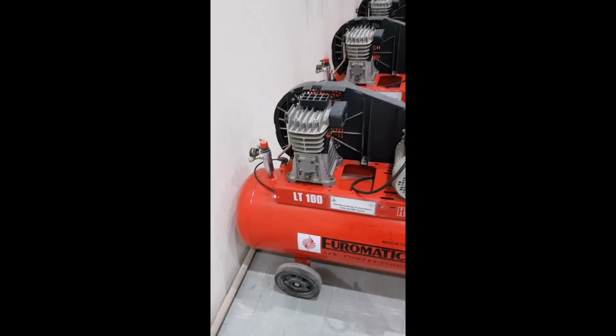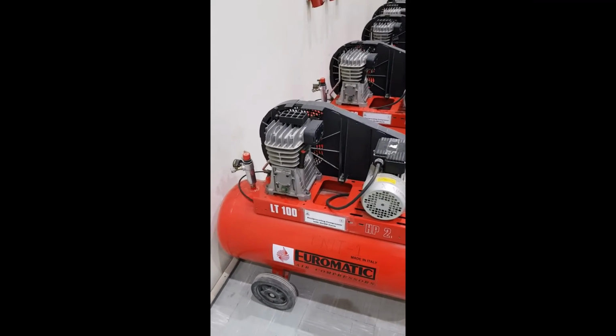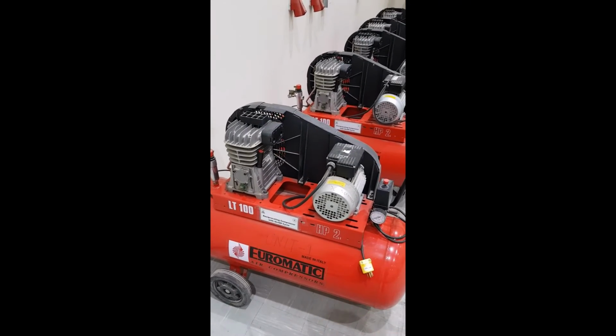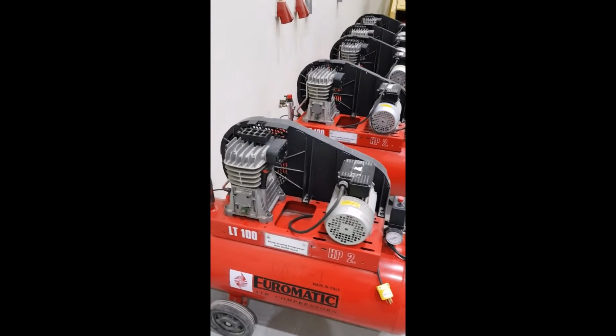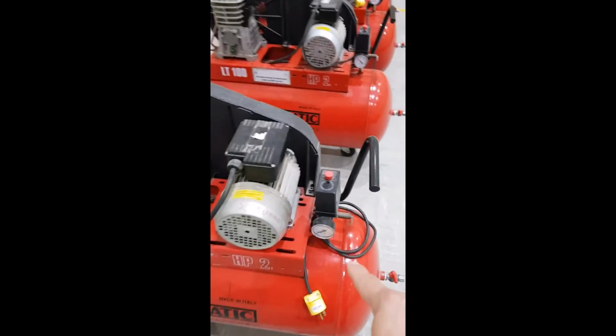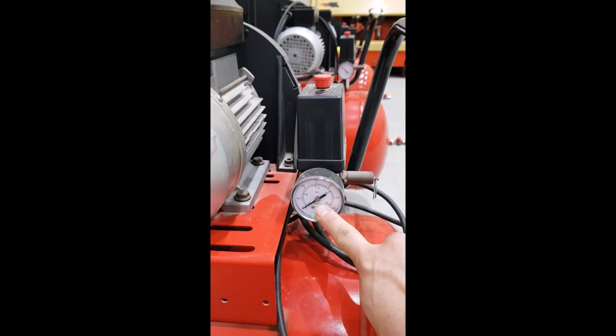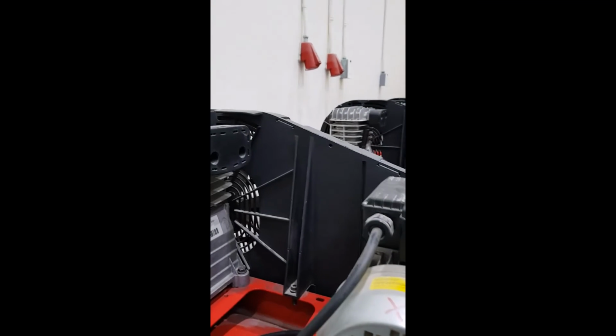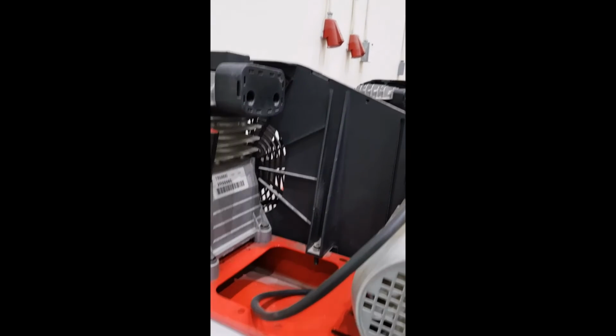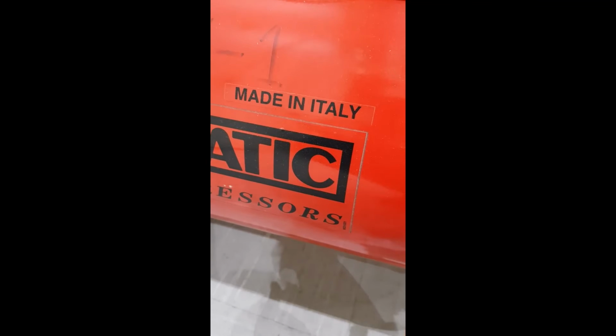So to recap, there are a number of maintenance tasks that we can carry out here. Number one, the pressure gauge: you need to make sure that it is reading correctly. Number two, we need to make sure that the belt tensioning is correct. Number three, we need to make sure that the tank does not contain any fluid, any water or moisture.